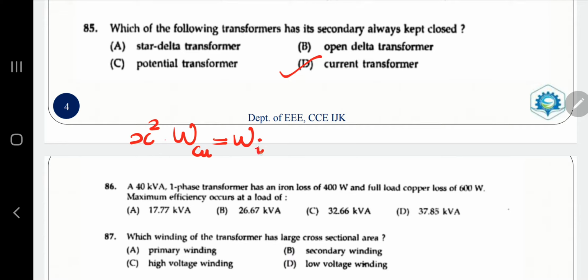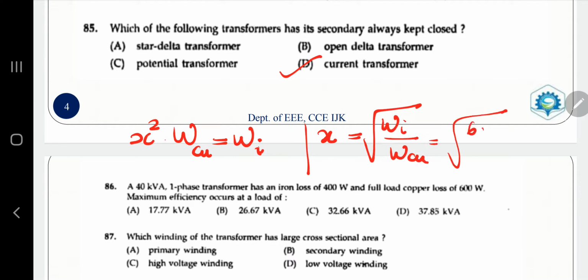The iron loss won't change, because it's constant for any type of load, but the copper loss changes with X squared. Now substitute to find X, the fraction of load at maximum efficiency. It is obtained by the root of Wi divided by WCU, which is root of 400 divided by 600. The load at which maximum efficiency occurs is X into 40 kVA, giving an answer of 32.66 kVA. The option is C. Let's move to the next question.